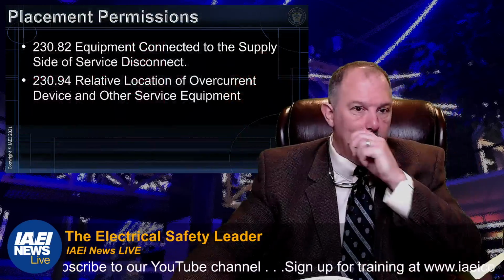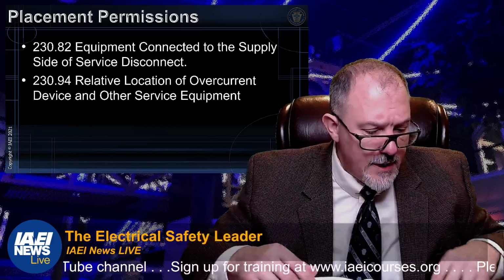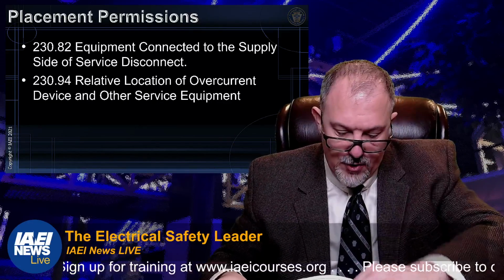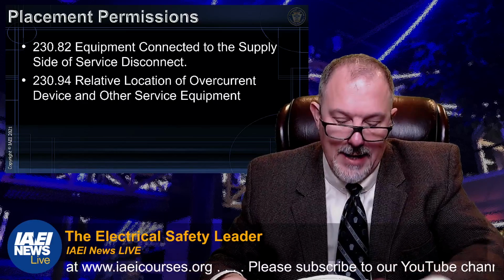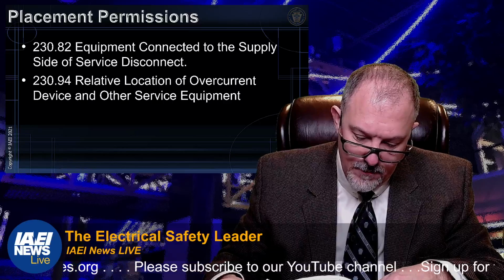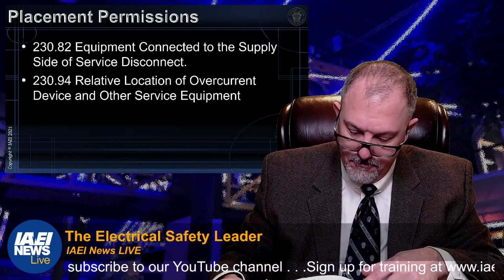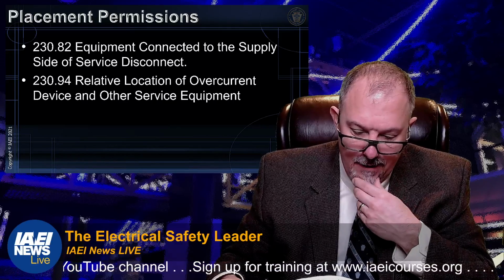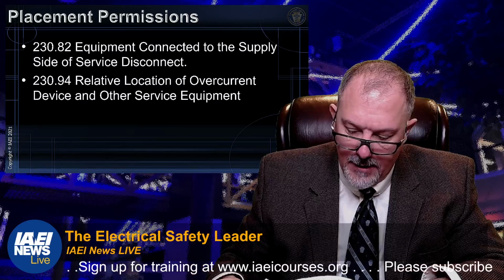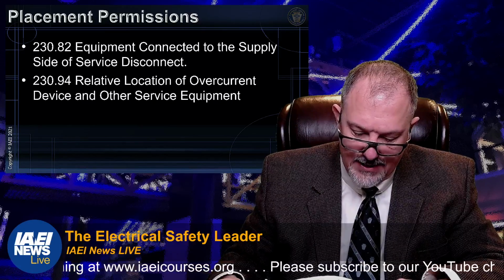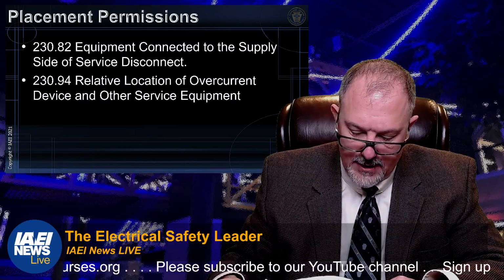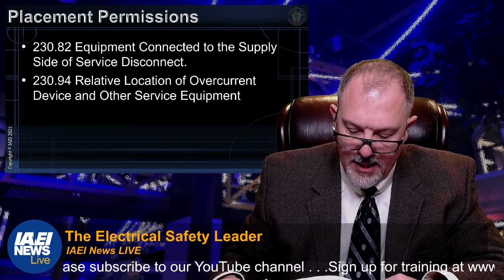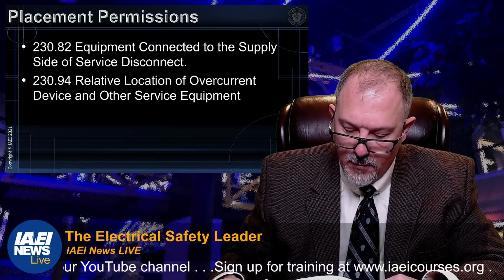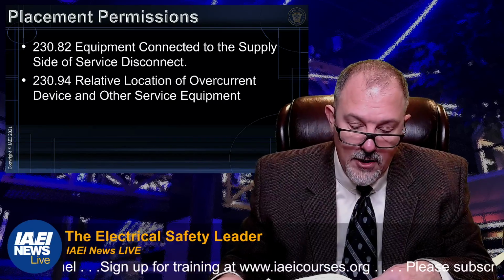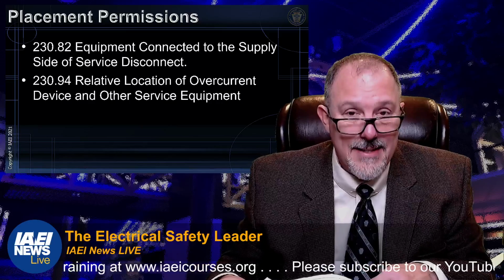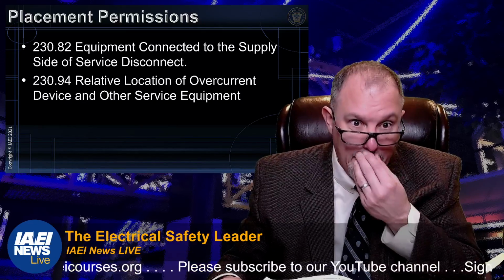Now let's take a look at the NEC. Article 230, service entrance, right? We made some changes in 230. 230.82 tells us what can be connected to the supply side. You have instrument transformers, you have conductors used to supply load management devices, circuits, fire pumps, you have solar photovoltaic systems, control circuits for power operable service disconnecting means, you have ground fault protection systems or Type 2 surge protective devices where installed as part of listed equipment, if suitable overcurrent protection and disconnecting means are provided. So 230.82 tells us I can put this on the line side of my service overcurrent protective device.